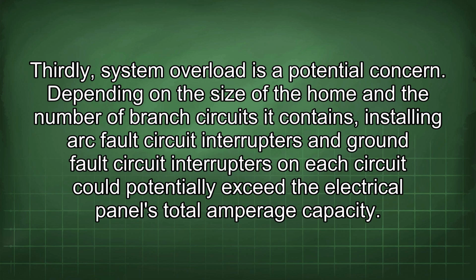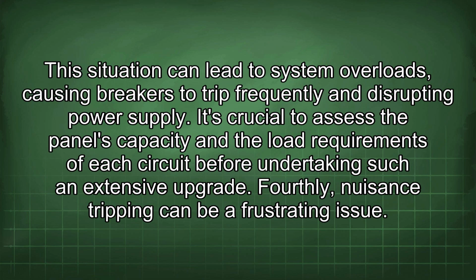Depending on the size of the home and the number of branch circuits it contains, installing arc fault circuit interrupters and ground fault circuit interrupters on each circuit could potentially exceed the electrical panel's total amperage capacity. This situation can lead to system overloads, causing breakers to trip frequently and disrupting power supply. It's crucial to assess the panel's capacity and the load requirements of each circuit before undertaking such an extensive upgrade.